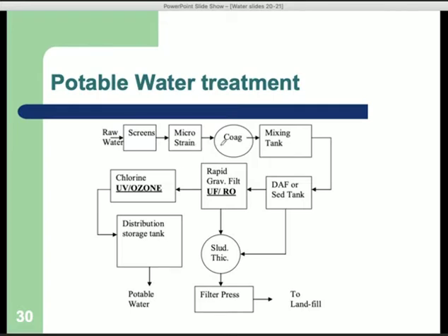And then you do the real trick, and that is the coagulation, which you will do with him, where you add substances to the water that bind all these small particles that would go through the sand filter. So the coagulants bind these particles into larger flocks, and the flocks then are larger than the sand granules, and therefore these flocks get retained in the sand filter.